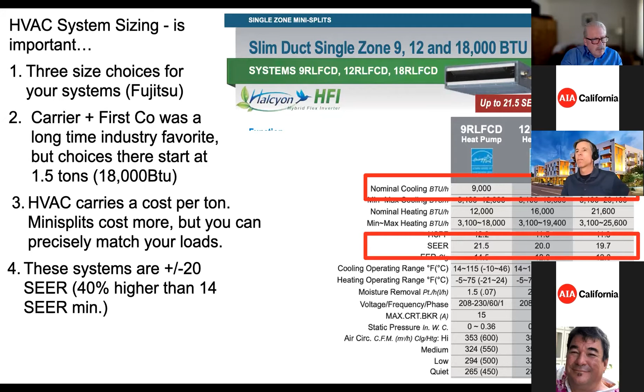The Carrier First Co option, which is very popular and still is in some cases, the smallest size that Carrier makes in a non-mini split version is 1.5 tons. So even if you only need 3/4 ton of cooling, your mechanical engineers, if they're still living in the 1990s, as many of them are, will say you get a 1.5 ton system. You've got to push them towards these other options because they're so much better.